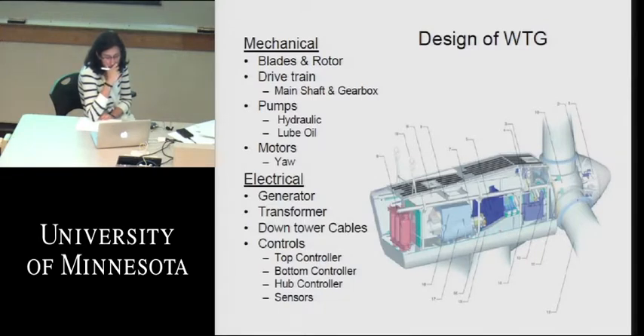You don't see it well, but item number 6 kind of shows a black box right behind that blue generator. And that is the main brain of the wind turbine, up in the nacelle. It's just a standard PLC-based control center for the wind turbine. All the inputs and outputs from the wind turbine, all the different systems and control decisions, have to go to that top controller. And it makes the communications out to the outside world also.